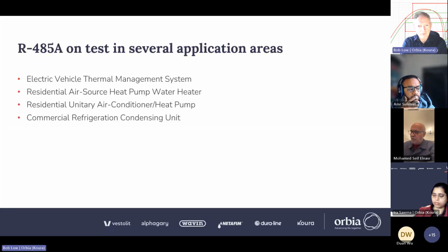The performance as a result is improved, and also with the lower operating pressure in practice, it can run to a much higher ambient temperature range than CO2 and still be acceptable in terms of the compressor performance. But we'll get into more of that as we go through the testing. So I have some numbers from different types of application here to share with you. The first is, again, one of these electric vehicle thermal management systems. This is a combination of air conditioning and heat pumping, and although it's maybe a little bit outside the normal remit of ASHRAE, which tends to be building focused, I'm including the data because it gives a good insight into the effect of ambient temperature and performance. And I've got some data on a residential heat pump water heater. We've done some work on an air conditioner heat pump as well, and I'm going to talk mostly then about commercial refrigeration, which is a live test project that we're running right now.